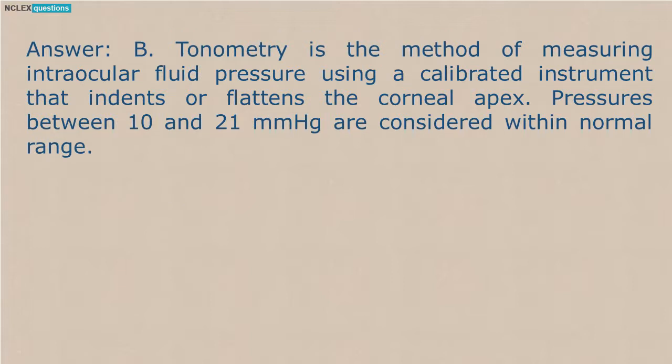This is a method of measuring intraocular fluid pressure using a calibrated instrument that indents or flattens the corneal apex. Pressures between 10 and 21 mmHg are considered within normal range.